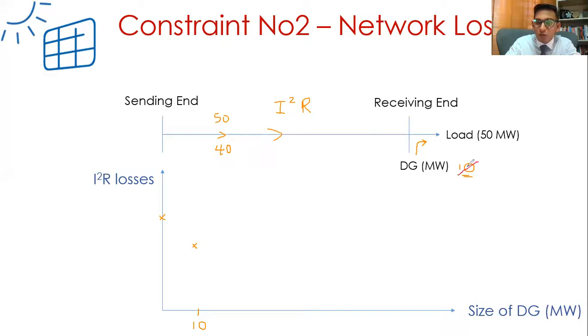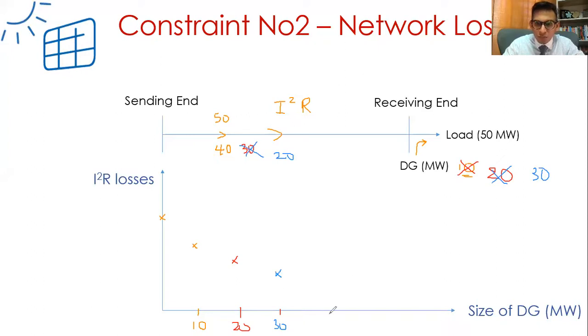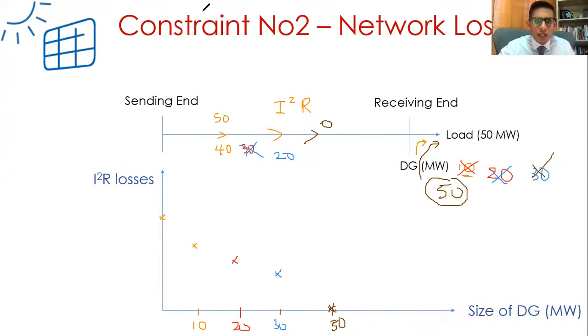If the DG produces 50 megawatts, the full power required by the load is produced locally - zero power flow from the grid, minimum losses. That's very good. But what if it increases to 60 megawatts? Now 50 is consumed, and 10 is going in the reverse direction back towards the grid to supply other localities. As the DG output keeps increasing - say to 100 megawatts - with only 50 megawatts consumed, 50 megawatts flows back, and we are back to the original loss level. If it increases above that, losses become worse than before.